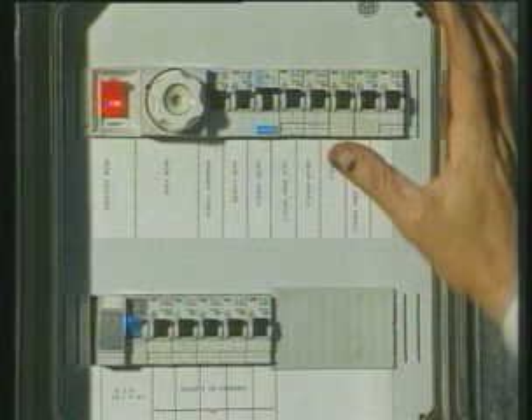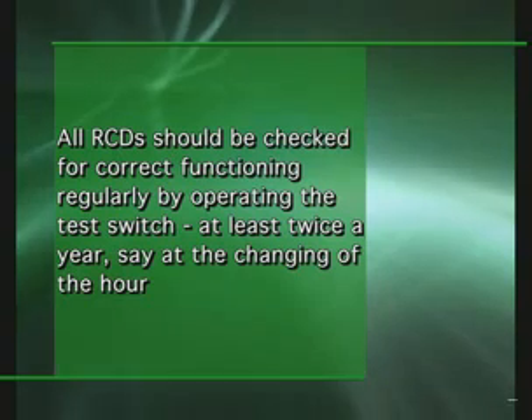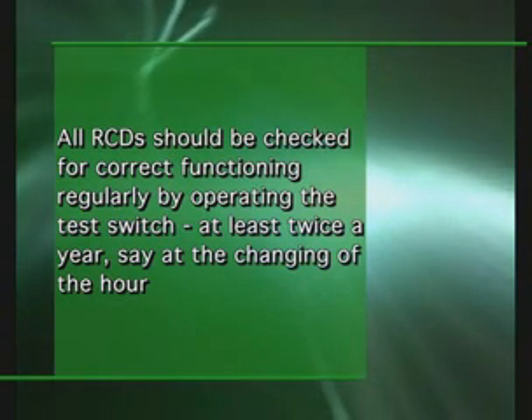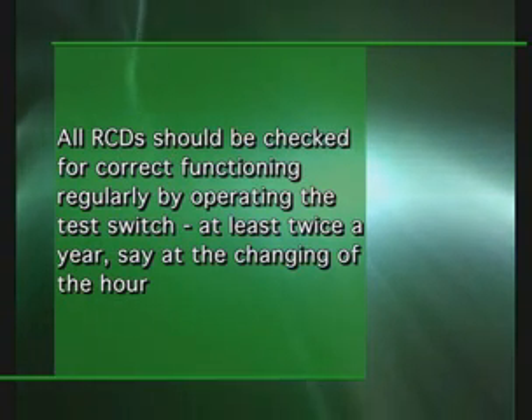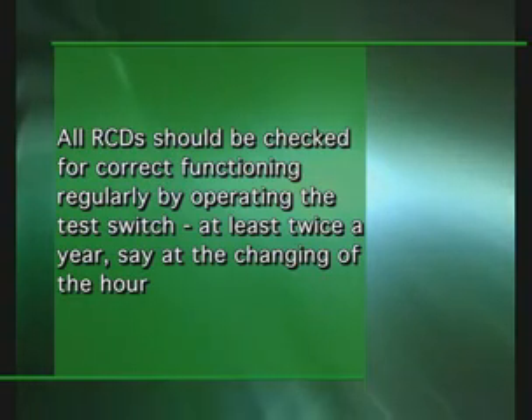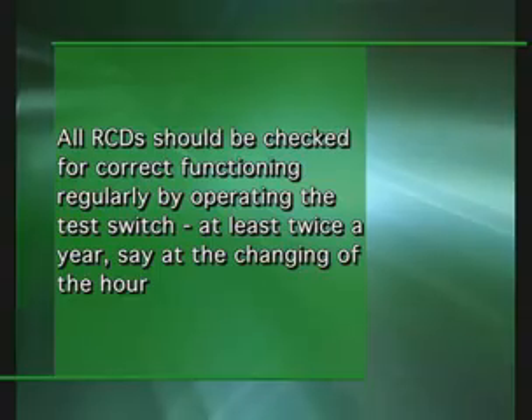It is a legal requirement that a circuit supplying a socket outlet must be protected by a residual current device, having a tripping current not exceeding 30 milliamps. All RCDs should be checked for correct functioning regularly by operating the test switch, at least twice a year, say at the changing of the hour.